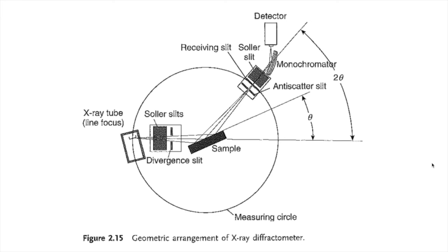All right one last sort of technical note here is the angle that we see theta is technically the angle between the incident beam and the crystallographic plane in the specimen that generates diffraction. So in most cases this is the same as the sample surface, it's because the sample surface is parallel to the diffracting plane but if there are some issues with that specimen being flat or in plane with the top surface then there could be some issues with that. So but just technically speaking the angle that we're measuring is between the incident beam and the diffracting crystallographic plane so that's just something to keep in mind with this geometry.